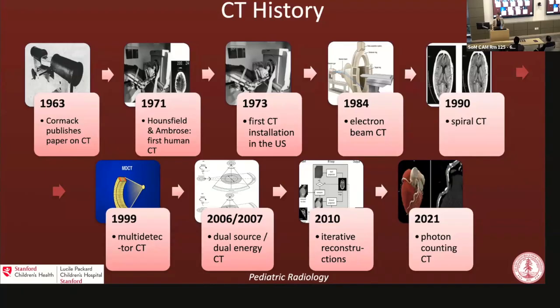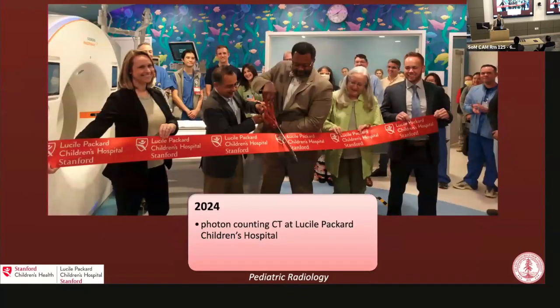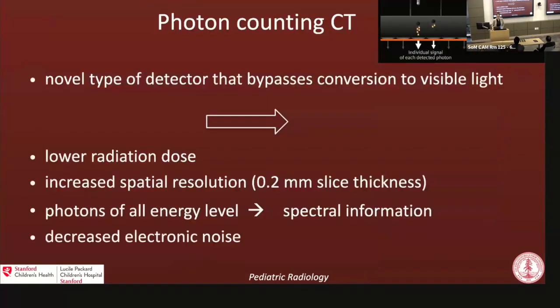Then in 2021, finally, that's quite recent, 4 years ago, the photon counting CT was developed. That's nothing about the tube, it's just the detector. That's the new thing to the CT. And then in 2024, last year, we got it finally here in the LPCH. So what's the difference? This detector basically bypasses the conversion to light. And skipping this step leads to low radiation dose, because there are no septa.